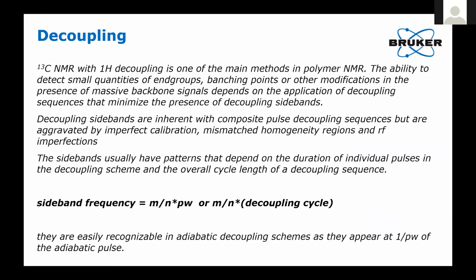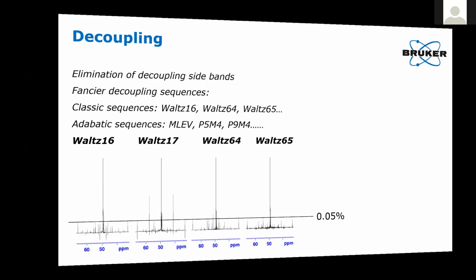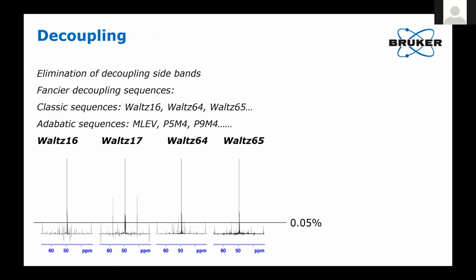One of the major issues in carbon-13 NMR of polymers is proton decoupling. Most of the composite pulse decoupling schemes will give you a certain amount of sidebands. These decoupler sidebands appear at positions which are related to the pulse width of the decoupling frequency and also the decoupling cycle. So whether you use WALTZ-16 or WALTZ-65 or whatever sequence you use, you get a different pattern of those decoupler sidebands. A lot of development has gone into decoupling sequences to minimize decoupler sidebands. So one way is just getting fancier sequences.